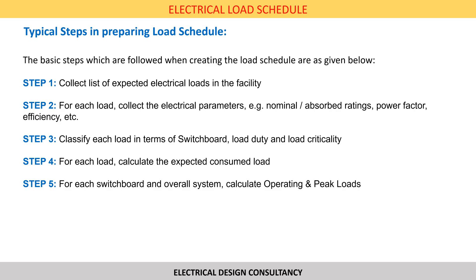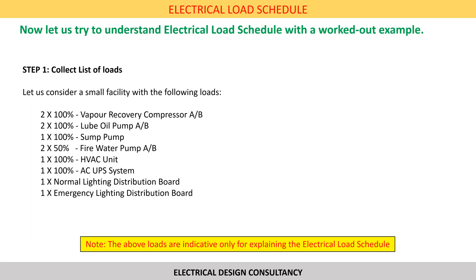Finally, based on the expected consumed load, we calculate the operating power and the peak load for each switchboard and the overall system. Let us try to understand the electrical load schedule with a worked-out example following the steps described in the earlier slide.